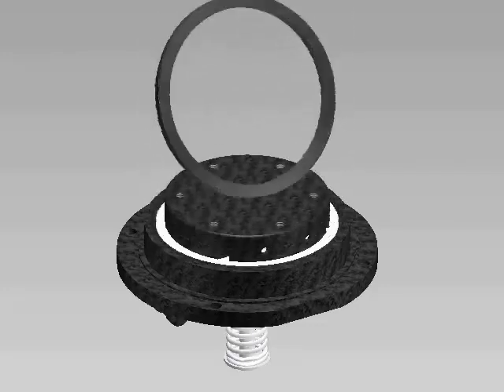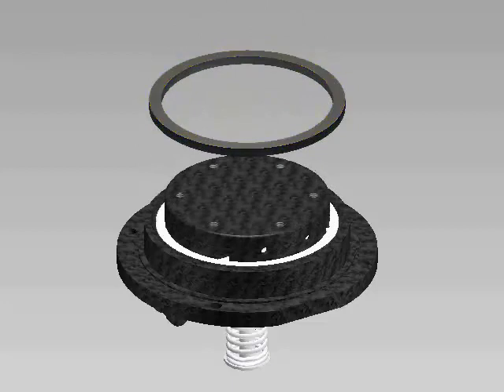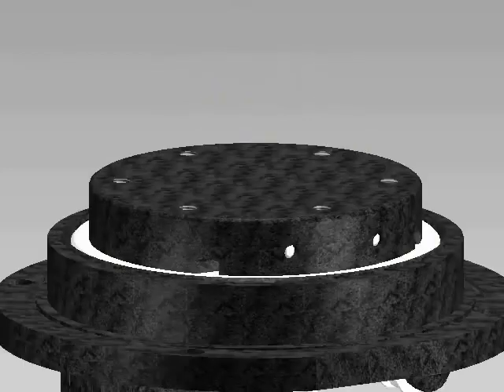Remove the seal ring and inspect the face for cuts or embedded debris. For a temporary fix, you can flip the seal ring over to use the smooth side while waiting for new replacement parts. Inspect the sharp edge of the seat with your finger for any damage.